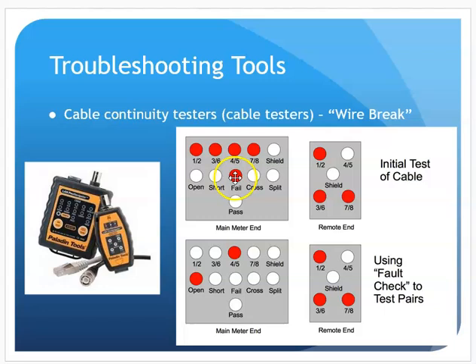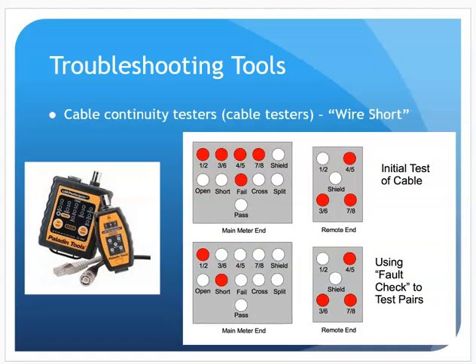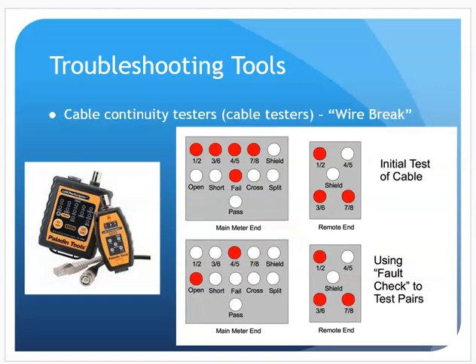It says there's a fail. As I go through the fault check, it'll let me know this particular wire pair is open. That's what I'm seeing there. That would let me know that wire pair is cut or not terminated or something. There's a break in the wire. If there's a short, two wires touching that shouldn't be, actually, let me back up here real quickly on the break. Wire break can happen.